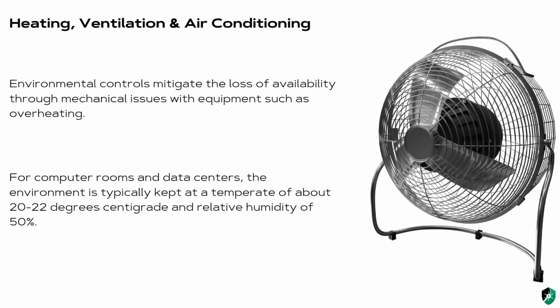Generally, for computer rooms and data centers, the environment is typically kept at a temperature of about 20 to 22 degrees centigrade and a relative humidity of 50%. I don't know if you've ever entered a server room before, but they are usually very cold. I remember when I used to work as a systems analyst and I had to go to the server room, I would always have to carry my sweater with me because it was a very cold place.